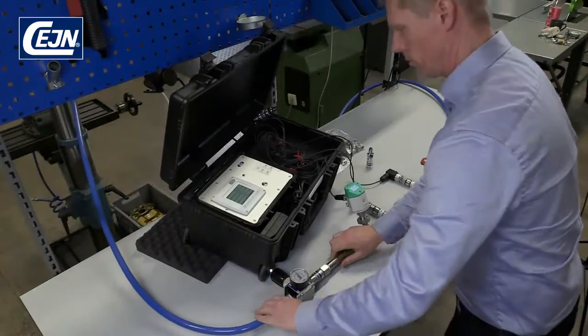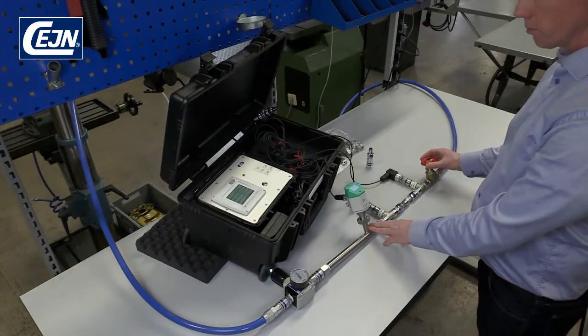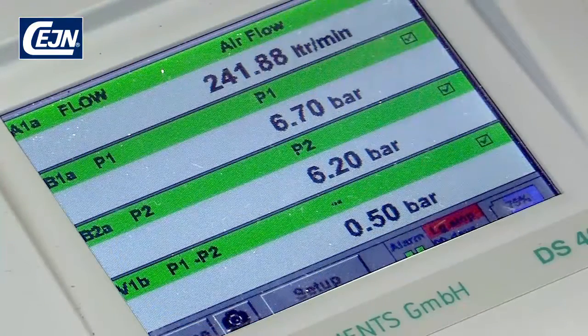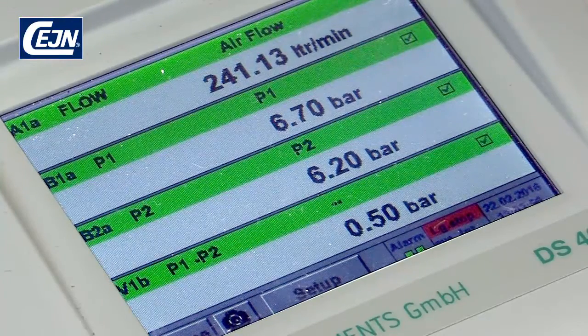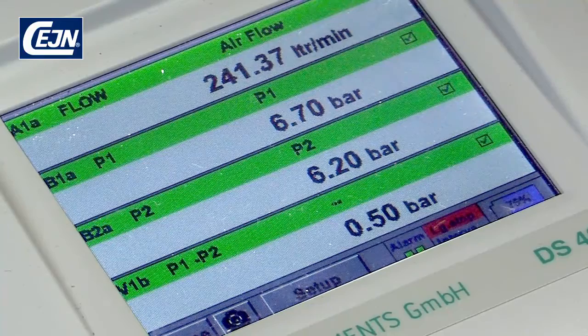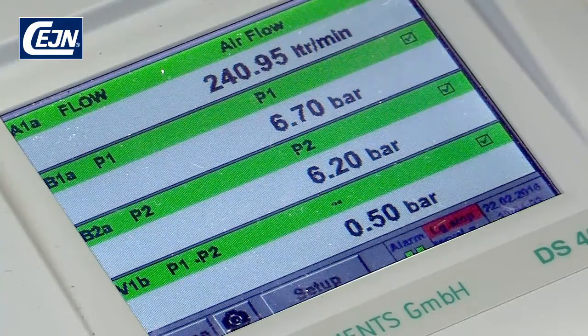Now we can start measuring the flow. If necessary, you can adjust the valve to achieve more or less the same value as before. In this case, it's impossible to make any adjustments as the coupling is inferior to the previous one. As you can see, the coupling is showing a reading of only 240 litres and the pressure drop is enormous.